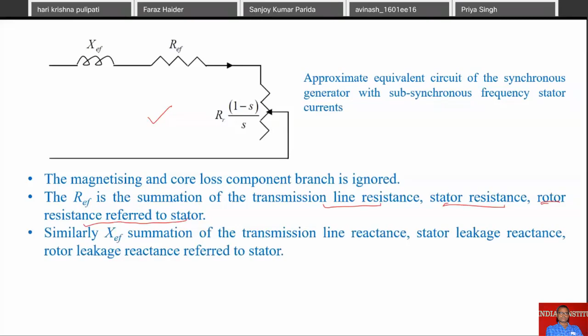Since the slip is negative, the variable rotor resistance becomes negative, leading to self-excitation in the circuit. So this rotor resistance is becoming negative because of the negative slip, and that will lead to the self-excitation in the circuit, and the oscillation will keep on increasing, reaching an unacceptable level. So this happens when this interacts with the rotor or the shaft. So we call it torsional oscillation.